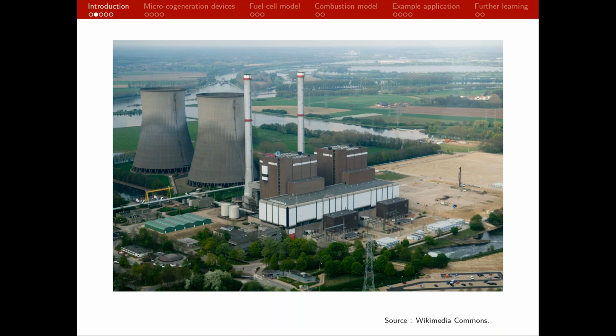This is a gas-fired system, in this case located in the Netherlands, but these systems look pretty much the same throughout the world. We take the fuel source, natural gas in this case, combust it, and take the thermal output through some kind of thermodynamic cycle—a heat engine, a Brayton cycle or a Rankine cycle typically, or some combined cycle—to try to convert as much of that thermal energy as possible into mechanical energy, and then eventually electrical energy, which is transmitted to the building site. But as you can see in this image, there are two large cooling towers at this power generation station, and that's where the waste heat is rejected.